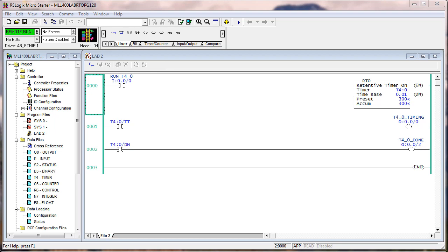However, with the Logix engine in the newer platform, you have 32-bit words. So if you use 1 bit for your sign, that leaves you 31 bits. That's a big number. With the older processors, you had to have the longer, if you want to call them that, time bases of 1 second. So you could at least get up to 32,000 seconds if that's what you needed.